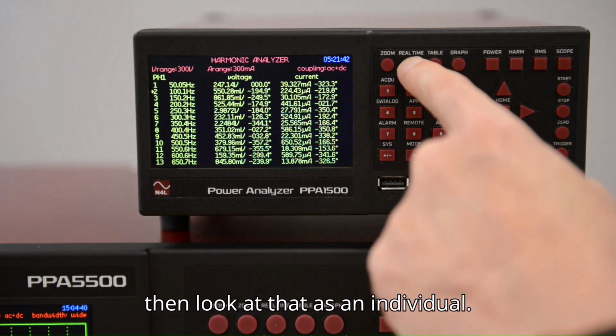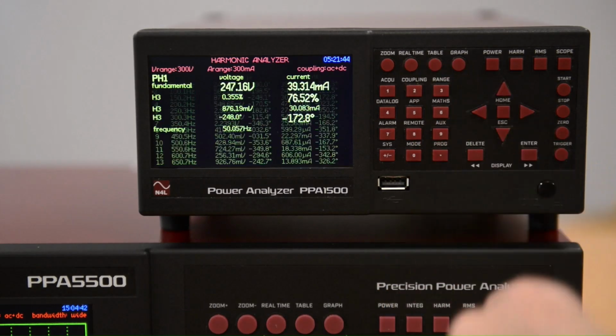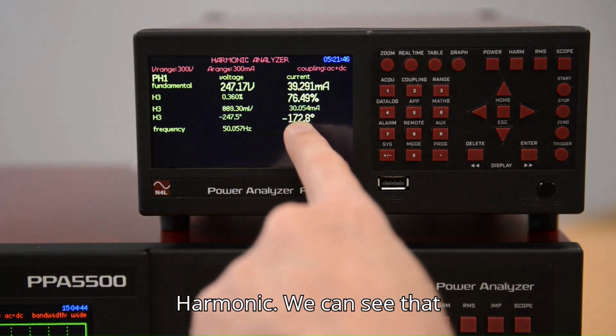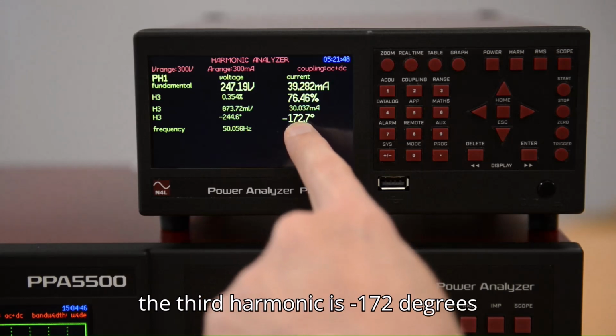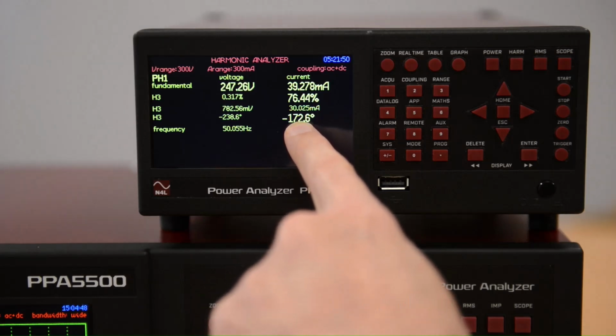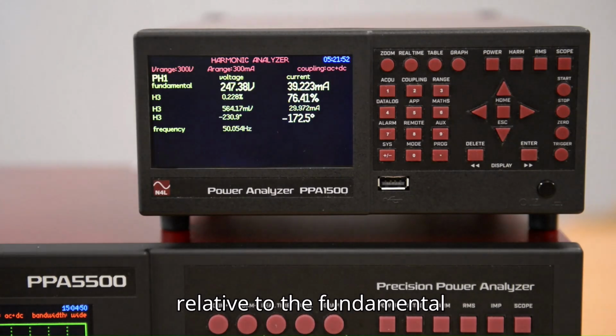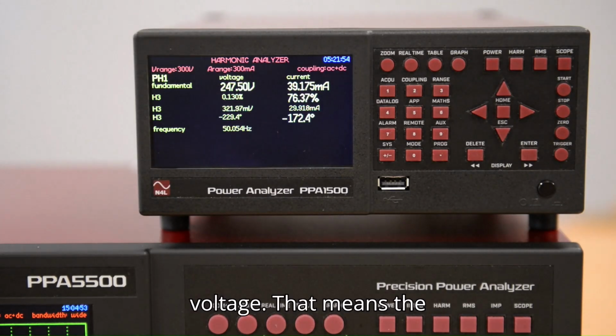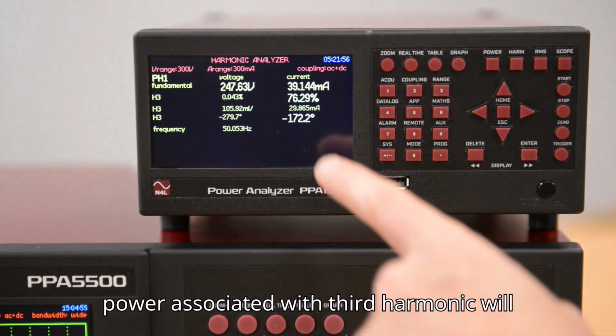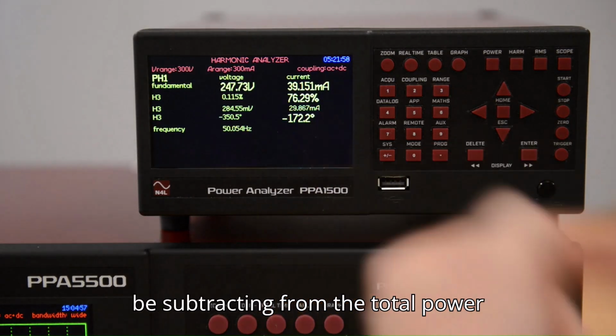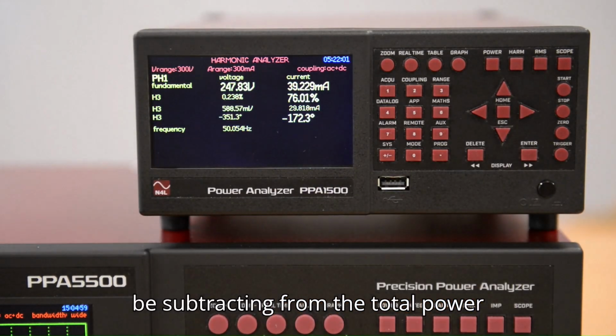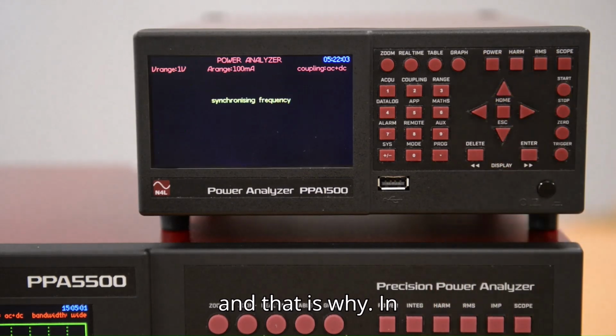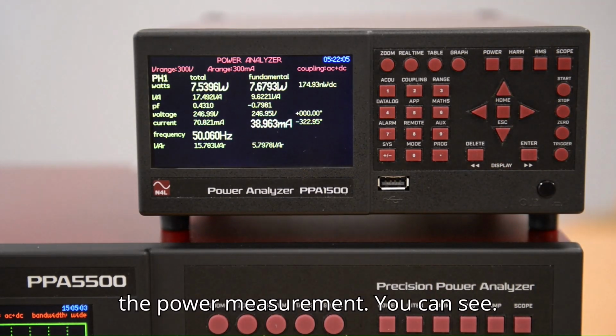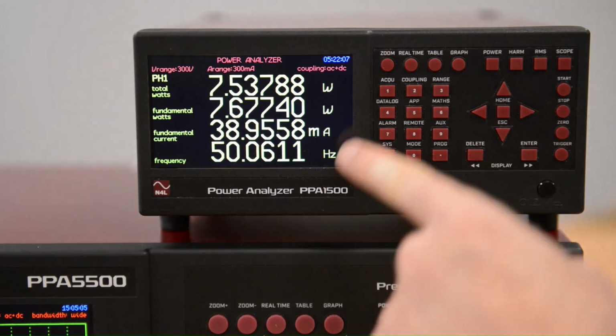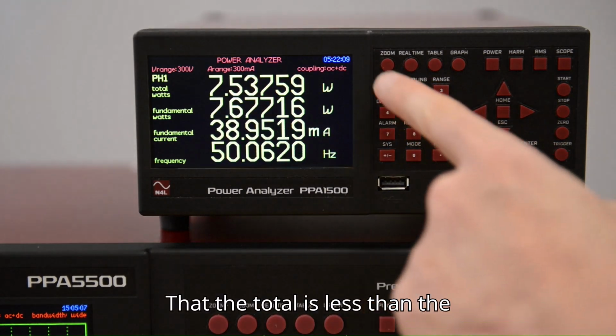Now, if we then look at that as an individual harmonic, we can see that the third harmonic is minus 172 degrees relative to the fundamental voltage. That means the power associated with third harmonic will be subtracting from the total power. And that is why in the power measurement you can see that the total is less than the fundamental.